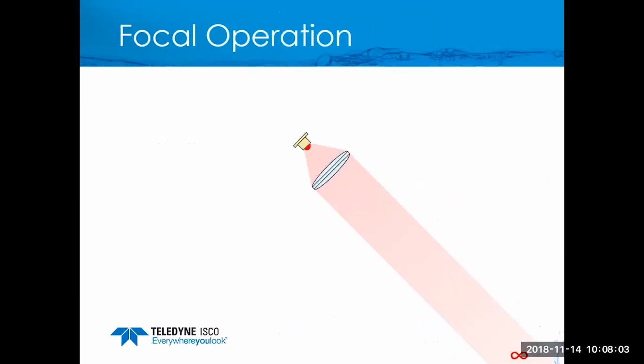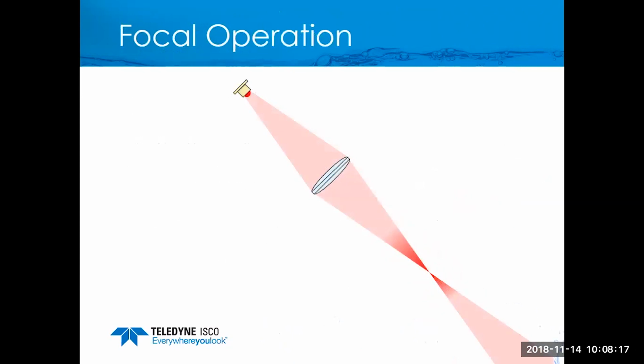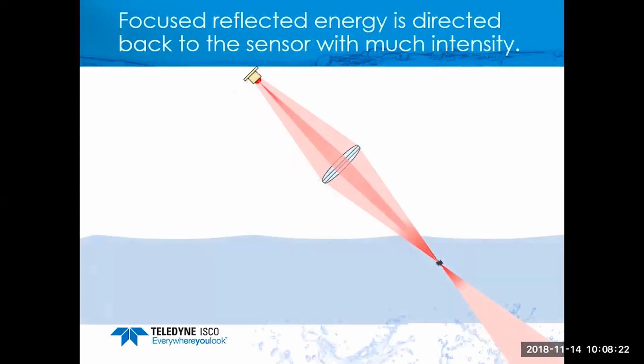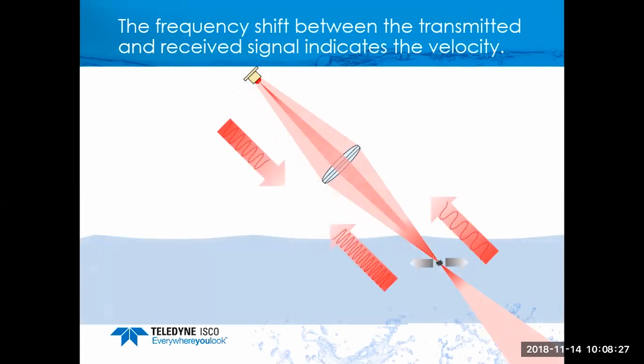Okay, let's talk about the operation of the laser. A traditional laser pointer has a fixed focal point. The magic behind the laser is how we focus it. We have optics in the laser itself. We know where the water is, and we focus that laser to get a very defined area that we're looking at for the velocity. That area that we focus on will give us our maximum reflected intensity, or light, from the laser signal.